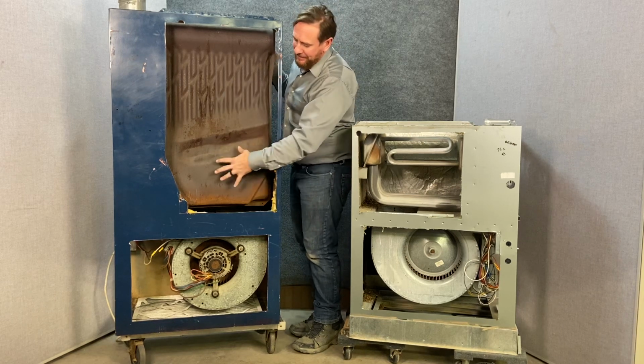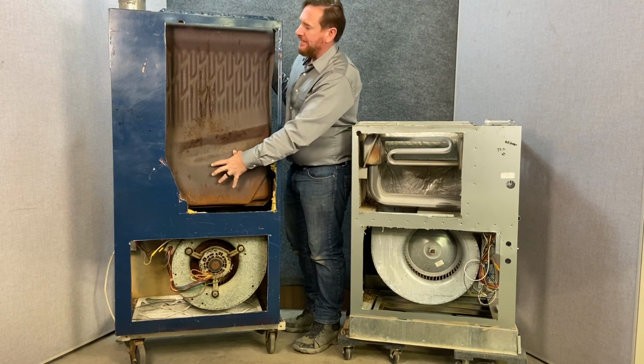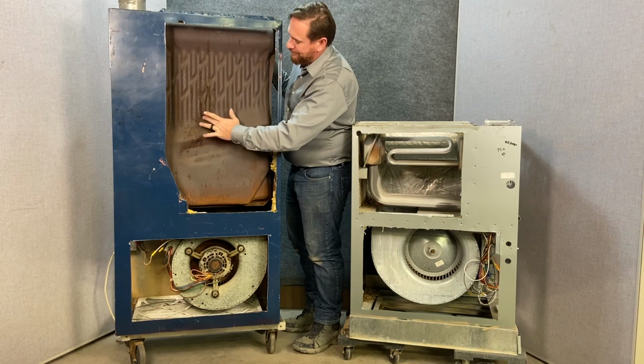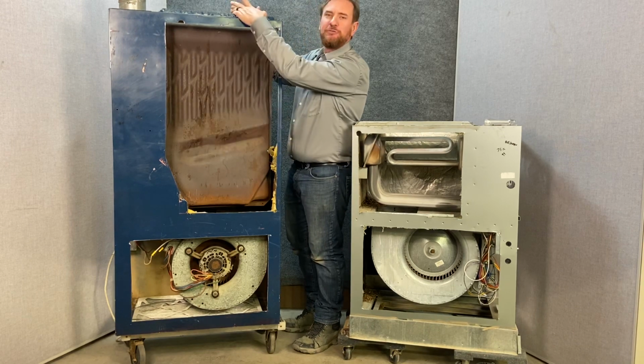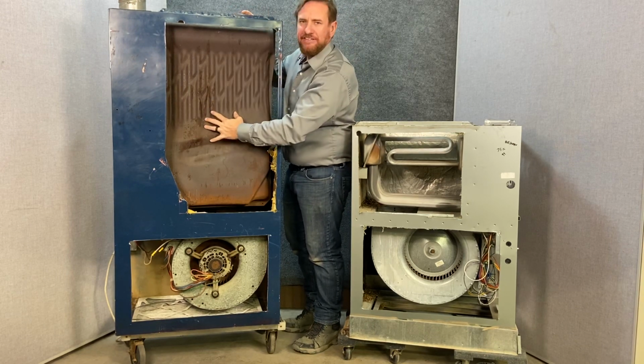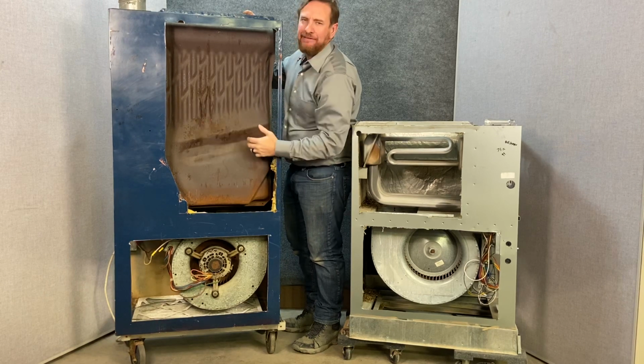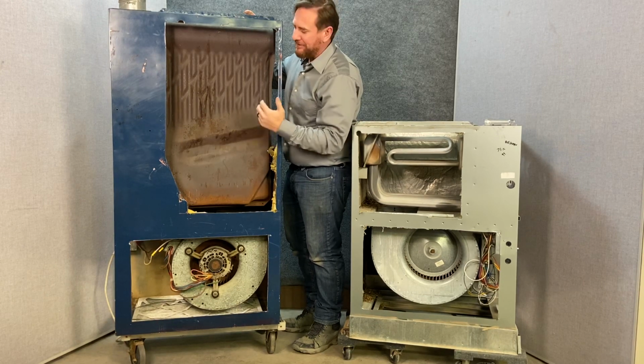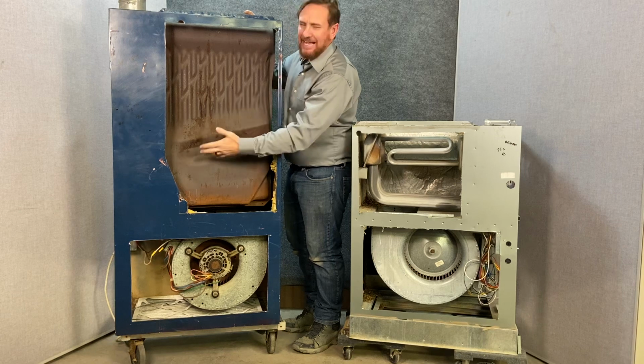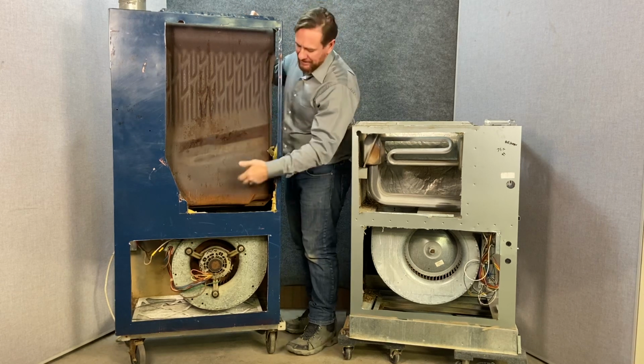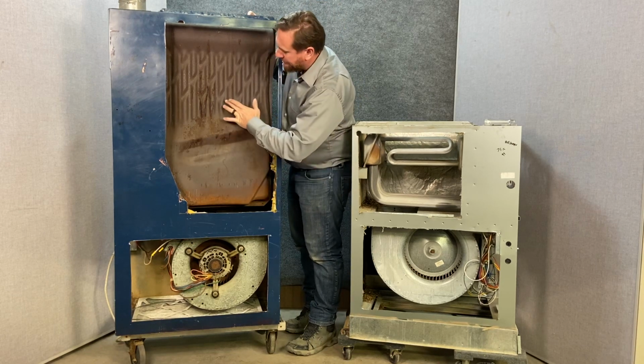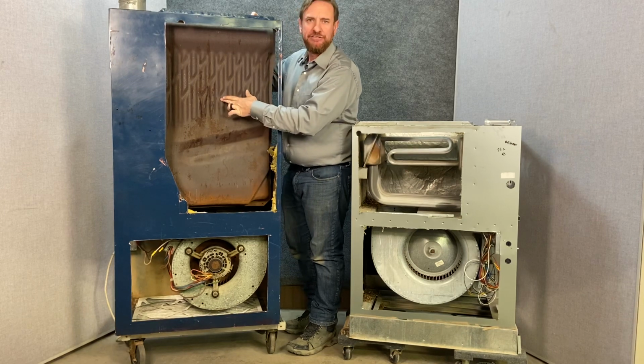The system here notoriously would rust out. You can see these very dark rust spots. The evaporator coil is most likely leaking, and these would rust out all the time. Plus, where that pilot light would be burning, it would be below dew point in several situations, especially in the summer, and it would cause these heat exchangers to rust out. Anywhere there was a seam, anywhere these little bends were common points for these to crack.